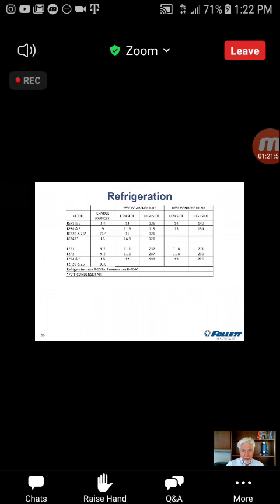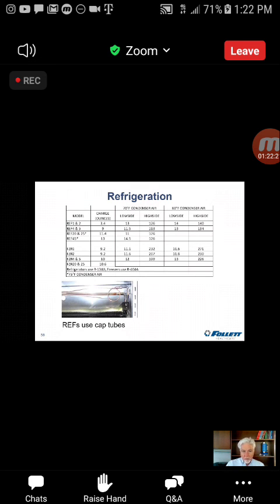Now, the exception to that is the original under-counter refrigerators. Those used R404A. They are distinct: they have the latch and the handle on the side of the door, and they do not have the plastic panel with the user interface across the top of the door. If you don't see the plastic panel, if it has a latch to open the door, that unit uses R404A. If that's not there, any others use R134A. So on these units, our refrigerators today use cap tubes on the countertops and the undercounters. On the freezers, we use thermostatic expansion valves, not capillary tubes.